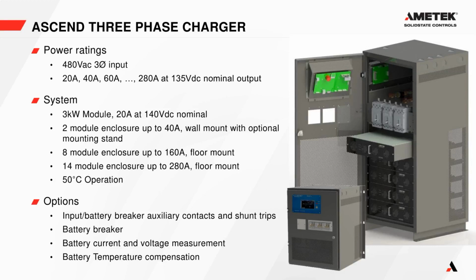Another option we offer is battery temperature compensation. So we have a 50 meter cable as the default, but we can have longer or shorter cables that go to the battery room and measure the temperature in the battery room. And then we will compensate our output voltage depending on some predefined or specified settings.